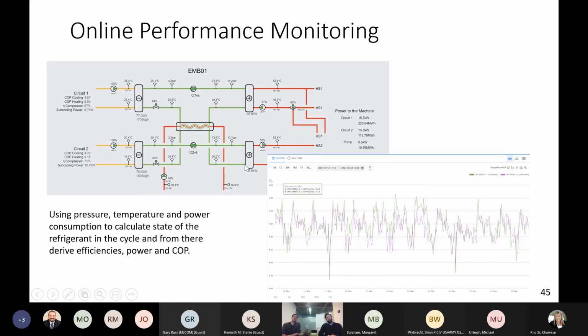If you have enough measurements of pressure and temperature in the refrigeration cycle, you can calculate the state of the refrigerant in each part of the system. From that you can derive how much power you're actually delivering through the heat exchangers at any given moment, and derive efficiencies for the compressors. You can get all the way to show the COP value, the efficiency of each individual heat pump as it's operating.